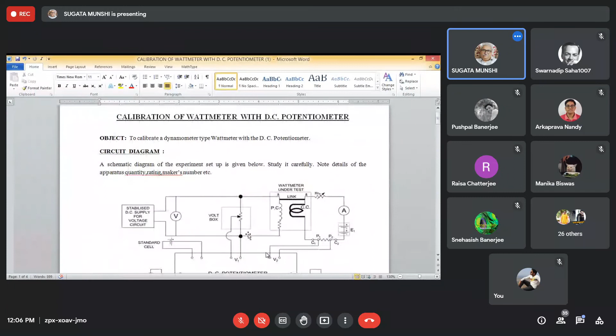This is the era of digital instruments. So why are we bothering about these analog instruments so much? That is because analog instruments cannot be completely rejected at any point of time. For example, I worked in a certain project, in a certain department. There we had a complete setup, different panels brought from Toshiba Corporation, Japan. All the voltmeters were digital voltmeters, with the exception of one voltmeter, which indicated the vacuum pressure of a certain system. The vacuum pressure ranged from 10 to the power minus 3 to 10 to the power minus 4 to as low as 10 to the power minus 8 millimeter of mercury.